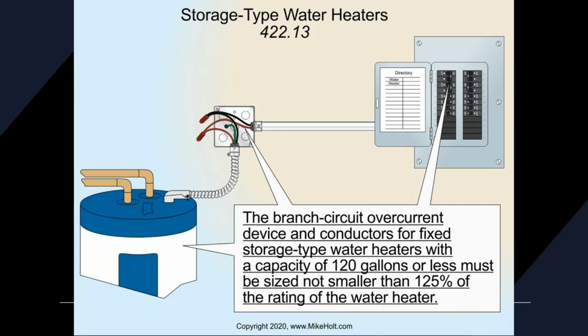It's buried back here in 422. They will say, what size breaker do I need for a 4500 watt water heater? Well, they would have the question worded where if you forgot the 125% rating on the water heater, because we consider it continuous use or whatever. Well, I'm assuming that's why they want 125%, but they have it worded in their question where if you don't multiply by 1.25, you'll get the question wrong.